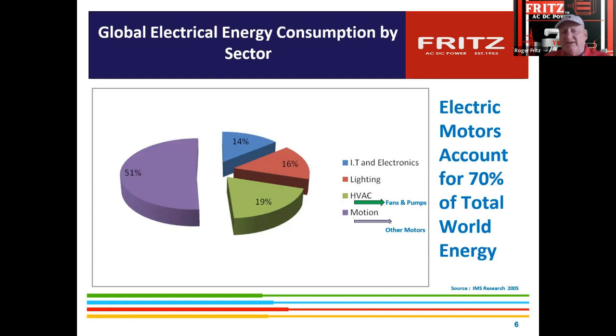Quite a bit of HVAC was done in certain areas where there were rebate incentives, but a lot of it still isn't, or they had a cap, like in New York, where they would do projects down to about 20 horsepower. They thought below 20 horsepower didn't really matter. The cost of equipment back then, 20 years ago, was kind of expensive. Nowadays they're going all the way down to a quarter horsepower. They're even putting it on what they call ECM motors, directly onto really small motors. But the main impact in HVAC is the chillers, the fans, the pumps, those big chiller compressors. Those need to be evaluated if they don't have drive controls.